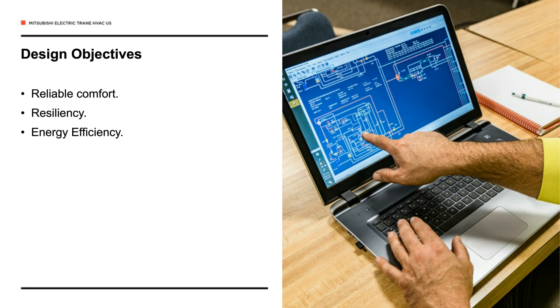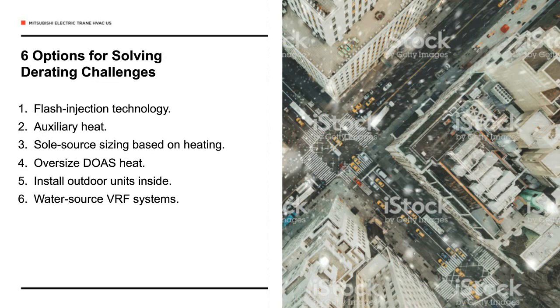If we look at heat pump technology from 20 years ago or more, we found that the heating capacity dropped off pretty quickly, started derating around 40 degrees Fahrenheit. And by the time you got to about 25 degrees Fahrenheit, you had really very little heating capacity, and usually would just, at that point, lock out the condensing unit and turn on some auxiliary source of heat, usually electric strip heat, which is a fairly inefficient way to heat the house or the building. So we'll talk about some specific approaches to solving derating challenges.